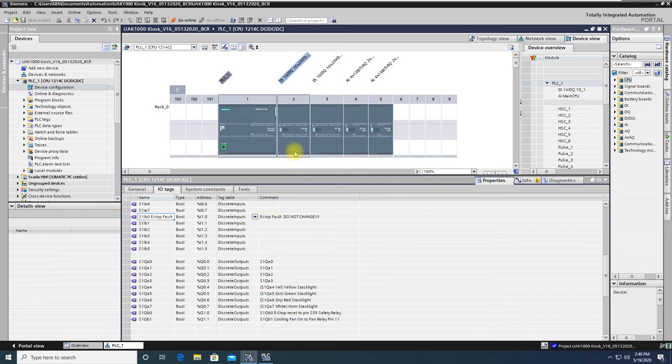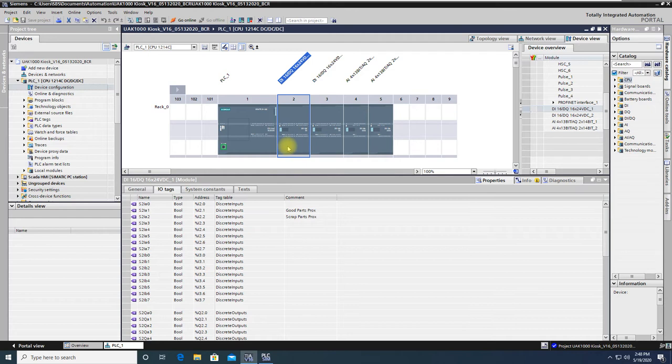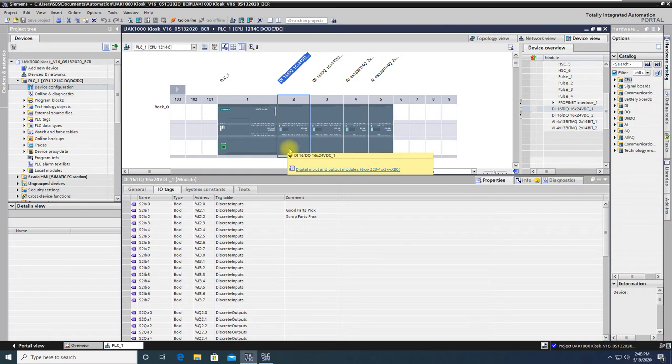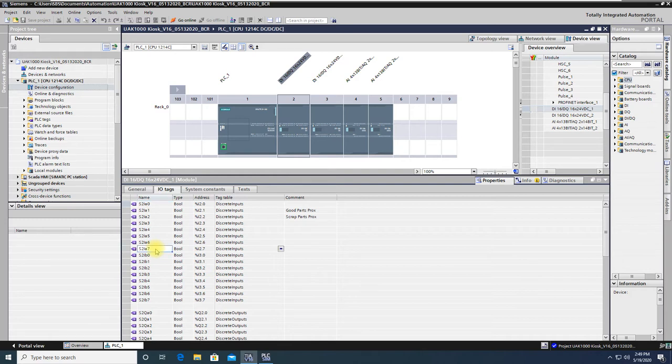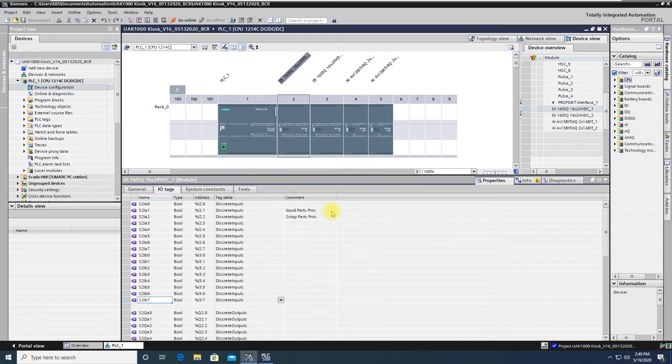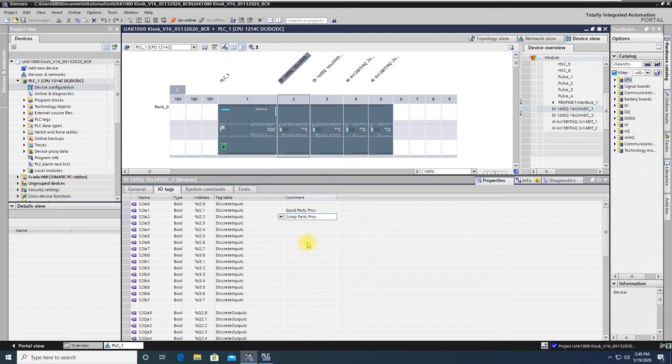We followed suit to the modules that are in slot 2 and 3. Those are both a combination module of discrete inputs and discrete outputs in one card. So in slot 2, you'll find 16 inputs. So I in the designation is incorporated with group A, bits 0 to 7, with the group B, bits 0 to 7. Any of those discrete inputs are available for use. Part of our software, we wanted to show off and demonstrate an OEE feature. So we've actually wired up for demonstration a good part switch and a bad part switch, so that you can see some numbers changing as far as quality of the product that you're making. But that's just for us. For our demonstration, of course, you can be changing them for anything that you see necessary.